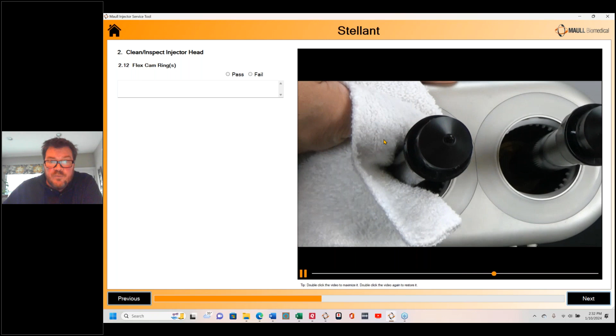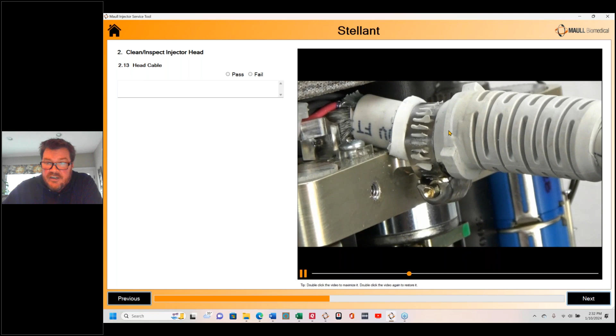Flex cam rings. These are these little white rings just inside here. It's just an inspection, really not a whole lot of cleaning that can happen because you have to tear this whole thing apart, but just get down there as best you can with a wet towel just to clean off the flex cam rings. We'll put pass. And this cleaning stuff is boring, I know, boring and repetitive, but there's a lot to it. Same thing here. Head cable. Going to inspect the integrity of the head cable and clean it off here where it actually goes into the injector head.